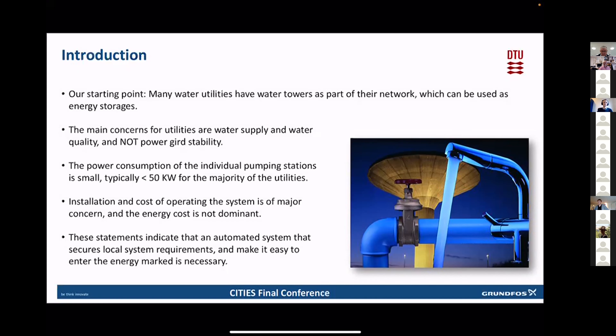Many water utilities have water towers as part of their network, meaning that they have potential energy storage as you move the water into the air, and then you can use that pressure to supply the system afterwards. However, before starting using such a storage, you need to be very aware that the concerns of the utilities is their supply and their water quality, and really not the stability of the grid. This means that any controls need to be in hand for the utilities, such that they can change it towards what is needed in their system.